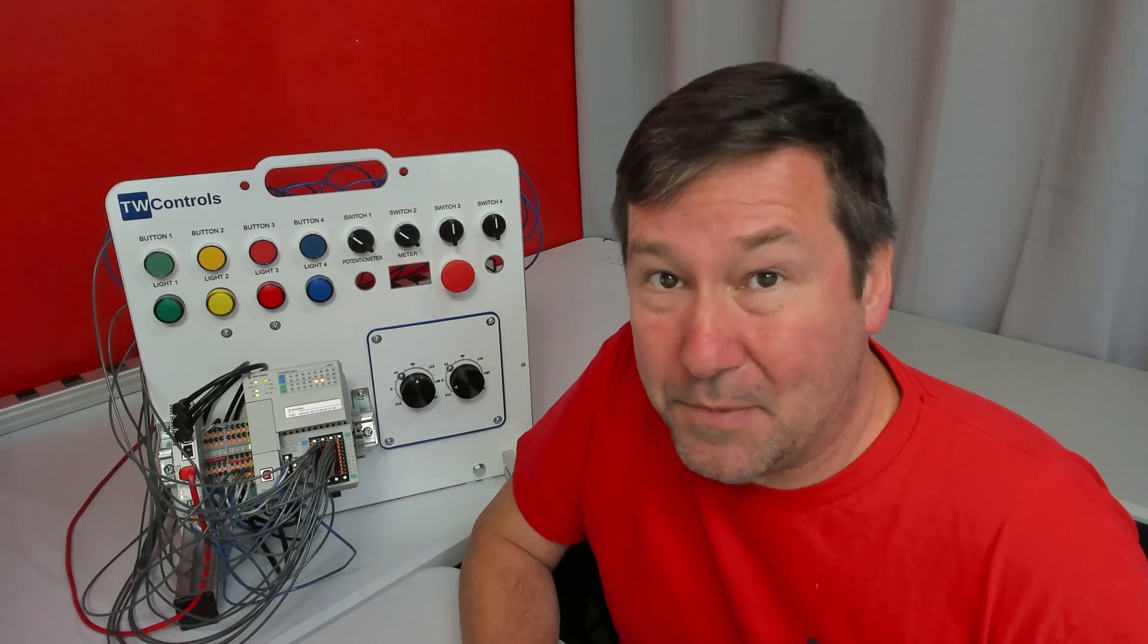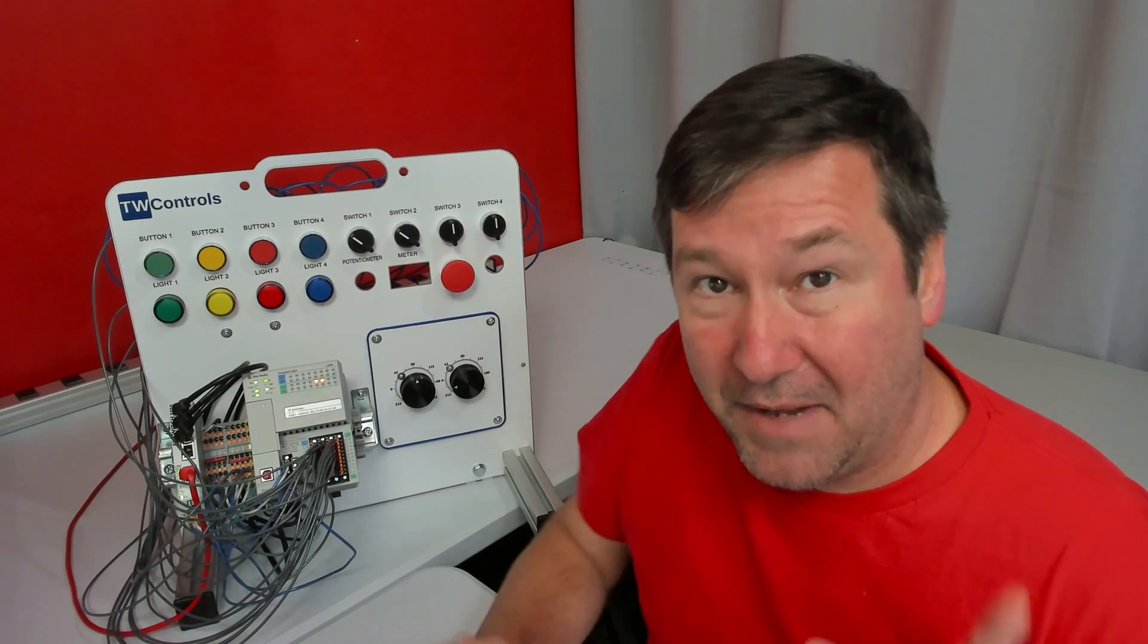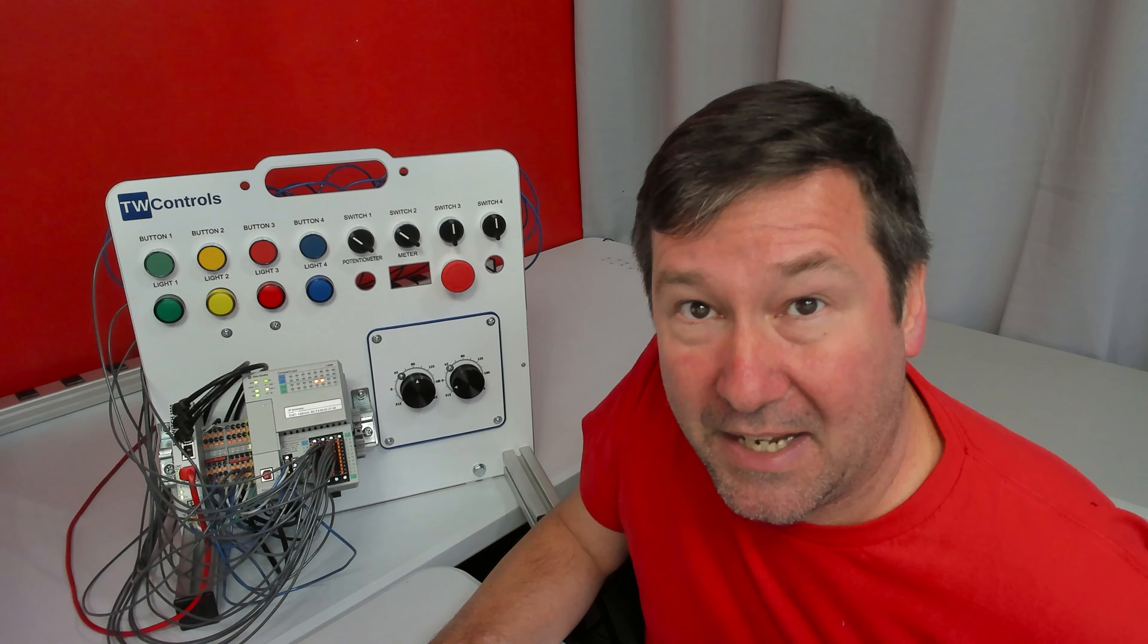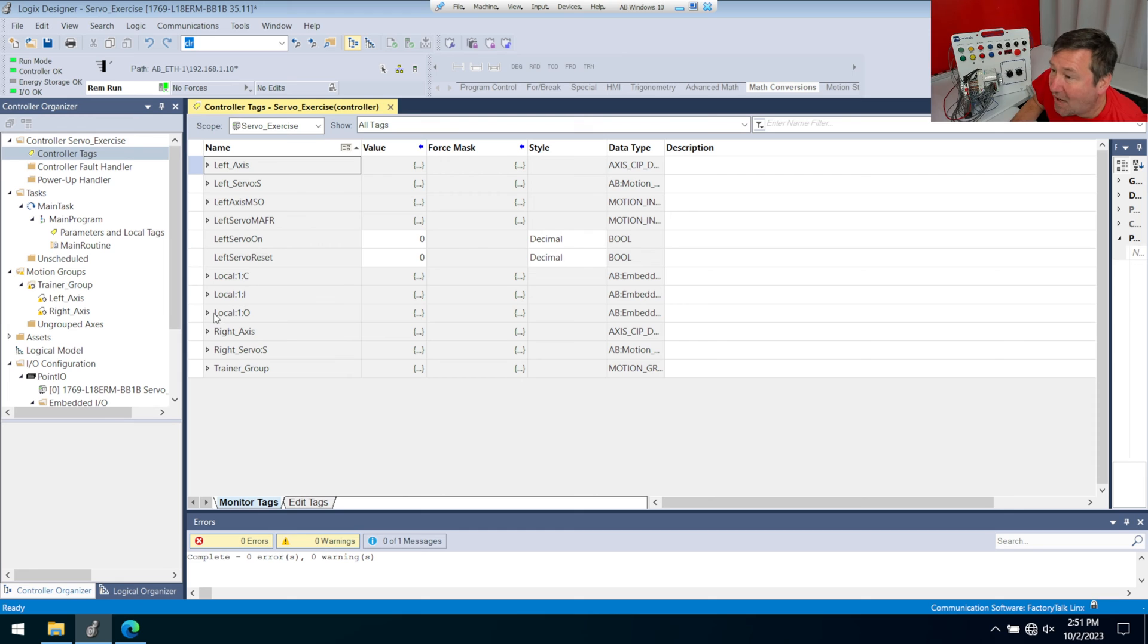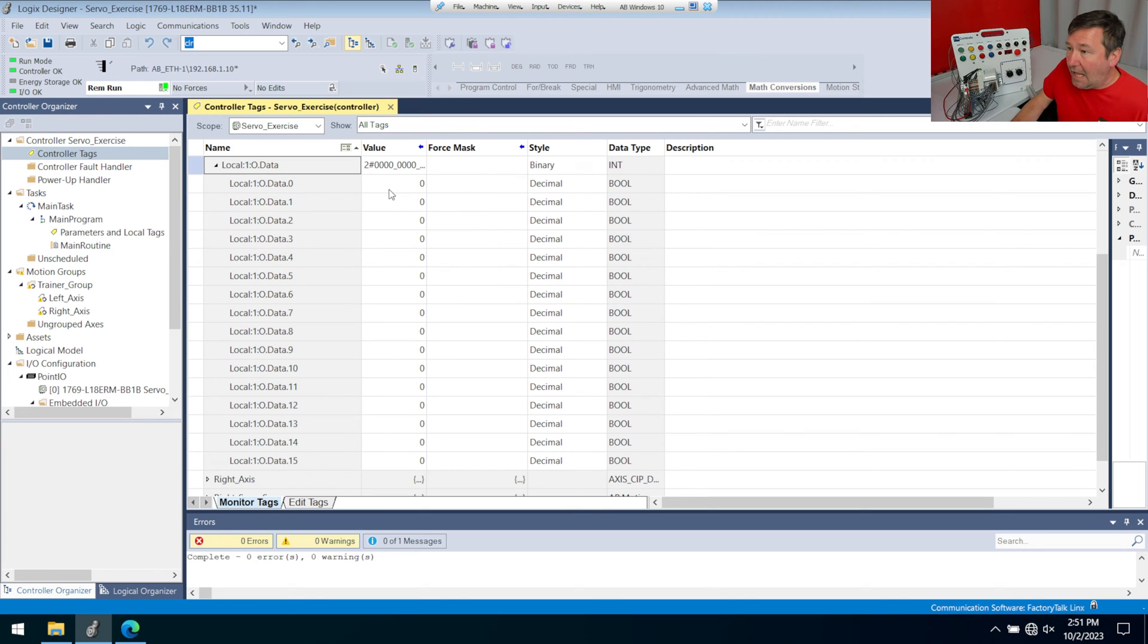Now we can test our outputs without writing any program. There are videos in the basic Studio 5000 series that go through this. While you're online, on the left pane find the controller tags, and then let's find Local:1:O, because that's going to be the embedded discrete outputs.